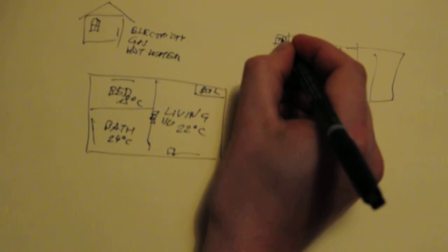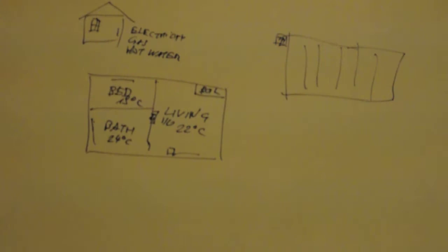Of course, it is well known that we can install simple thermostats on the radiators. But these thermostats are very sensitive to the change of temperature on the heater itself, so they have a very wide hysteresis of turning on and off. So in fact, we use more energy than is enough to raise the temperature to the desired level.